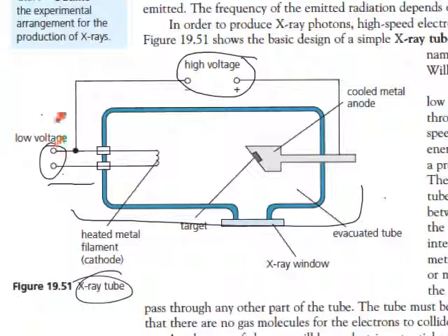Well, that's what this other big circuit is for. Now, these can go up to 25,000 volts or even higher, depending on some sources. But they connect up to the anode here. So this is a strongly positive anode. And what the anode will do to the electrons that are accumulating loosely here, they basically attract and pull off the electrons so that they stream across.